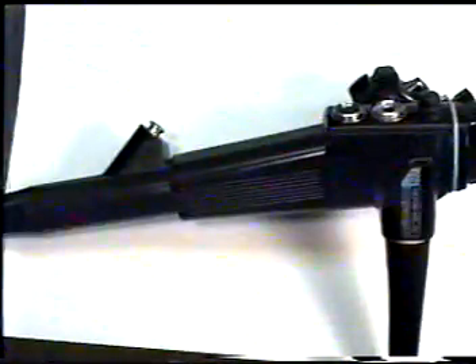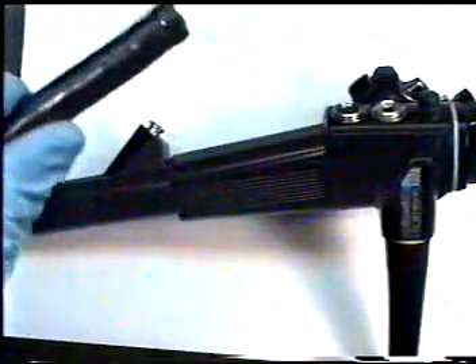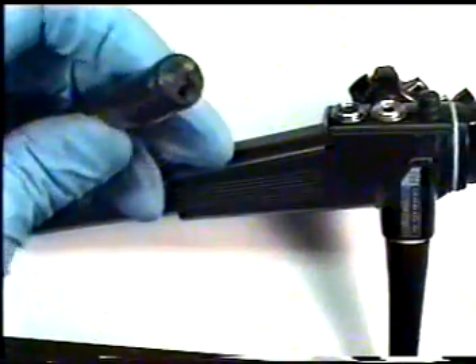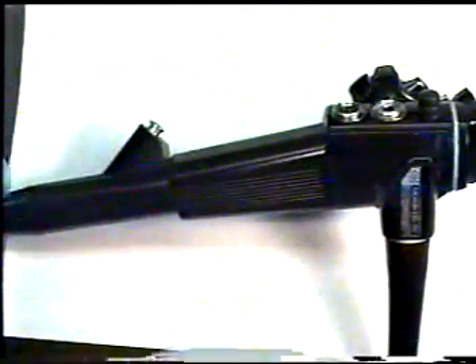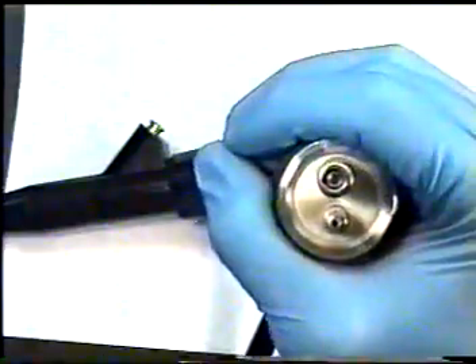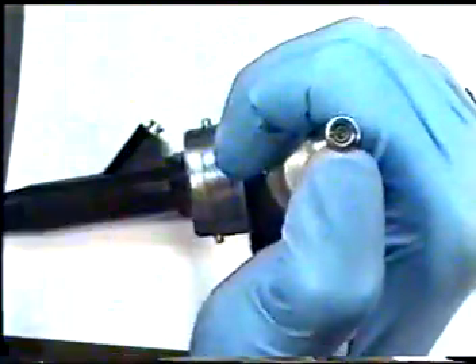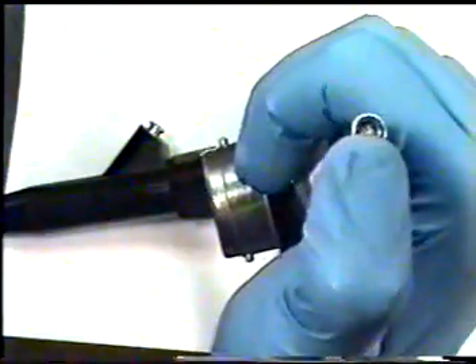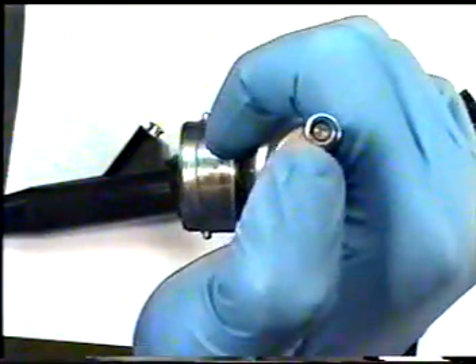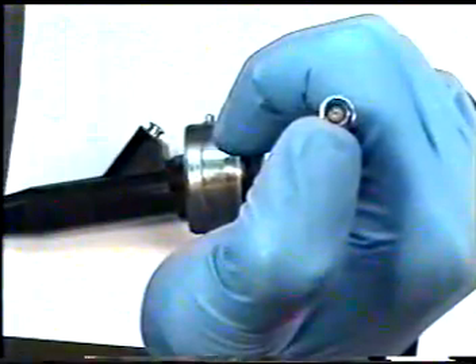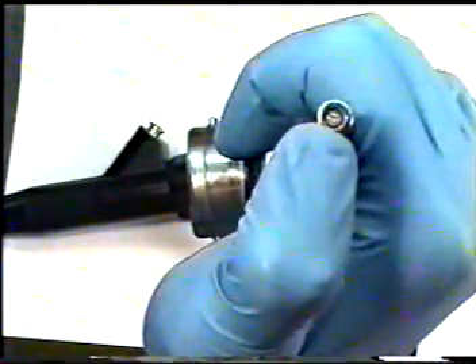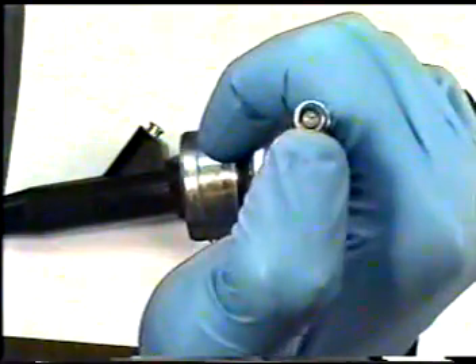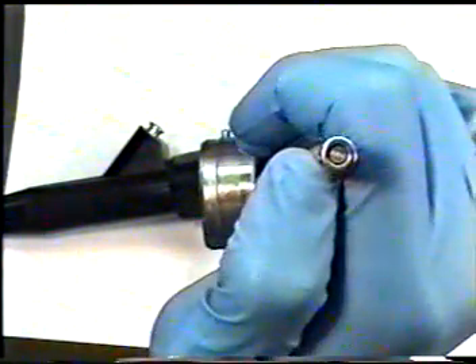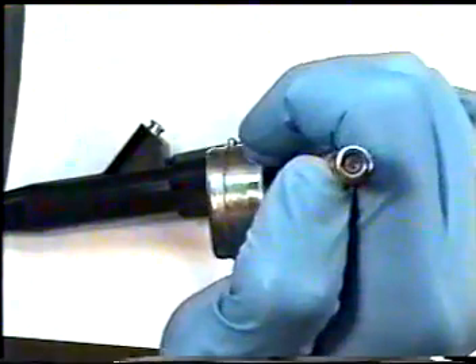If during the procedure there is a complaint of poor light, the best way to check your light guide or illumination bundle is to hold the distal end of the endoscope up to a light bulb or fluorescent light fixture. And while holding, look on the proximal end of the endoscope and check the light which is emitted through the scope. If it is poor, it will need to be replaced. It should be a full round amount of light coming through the proximal end of your endoscope. If it is not, again it will need to be replaced.